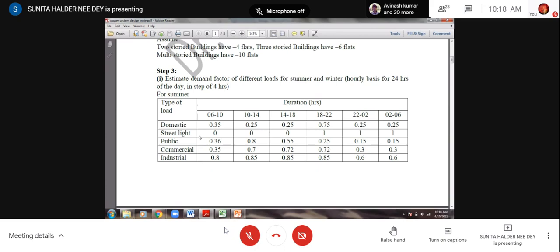No, this is required. Say you take it on an hourly basis. Now just assume what the demand may be, how demand may vary in a day. Obviously, on a 4-hour basis. So we have assumed here a 4-hour basis to draw a load curve. What deviation you have taken? From there you are estimating how load will vary in your subblock. Now from step 3 onwards, all will be subblock basis calculation. Why is it required? Have you understood how I have estimated the demand factor of different types of loads? The question you ask, I shall explain later.